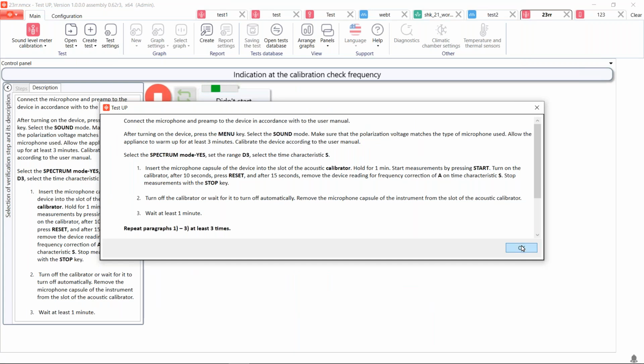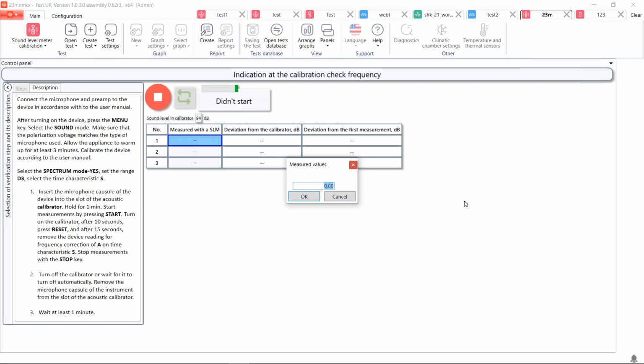And we are starting to get the result. While we're getting the result, I would like to tell you about the basic measurement error of the sound pressure level. It should not exceed plus minus 0.7, and it means that the maximum value possible should be 94.7 decibel, and the minimum possible value should be 93.3 decibel. So the first value that I got is 93.8.